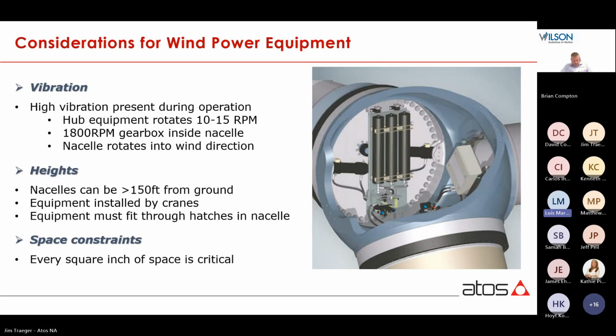Considerations for wind power equipment. There is high vibration present on these units. The hub equipment rotates around 10 to 15 RPM, and there is a gearbox inside the nacelle that rotates around 1800 RPM. And also the nacelle rotates into the wind direction. The height of these turbines, these nacelles can be more than 150 feet from the ground, and equipment is installed by cranes. And there is also equipment inside the nacelle that must fit through the hatches, so there are space constraints. Every square inch of space is very, very critical.